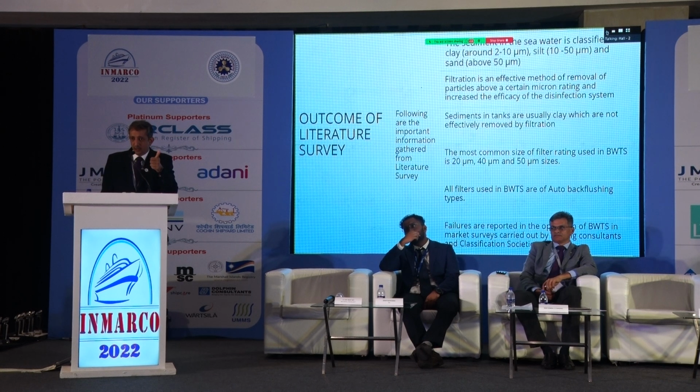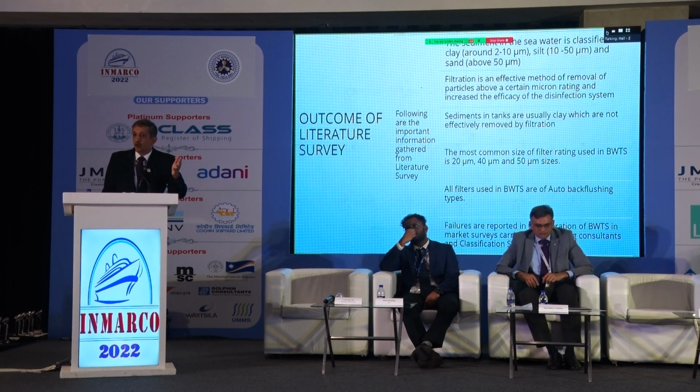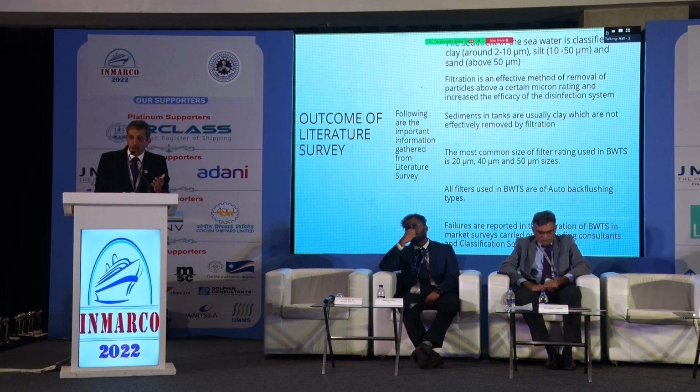First step is the microparticle, that is, particles of the size of the filter. Second would be slightly smaller than that, and third would be the slime layer and the clay layer which builds up on top of that, which we call caking of the filter. So these are the 3 steps that take place, and this is something which is not required to be researched on. This is quite evident in our shore-based research also. And all these filters use backflushing, which basically makes the water flow in the opposite direction.